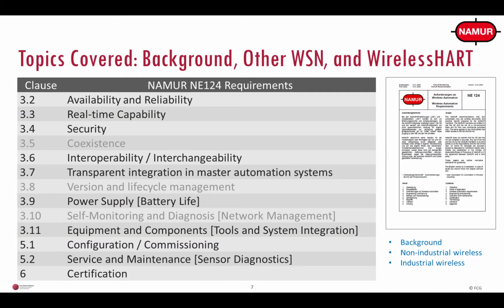So against that background, we will cover selection criteria for wireless sensor network for the plant. The requirements come out of the NAMUR NE124 recommendation. NAMUR is an organization of process automation users. So these are real end user requirements. So for each requirement, I will provide a little bit of background on why it's important, explain the limitations of non-industrial technologies. That is the reason you should not use non-industrial networks in plants. And lastly, I will explain how an industrial wireless sensor network tackles the issue. That is the reason you should use an industrial grade network in plants.